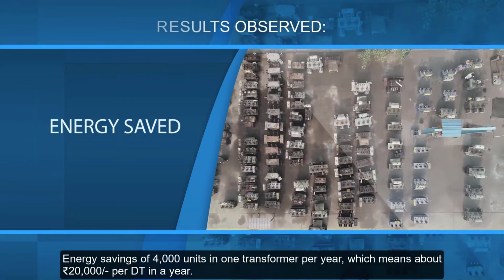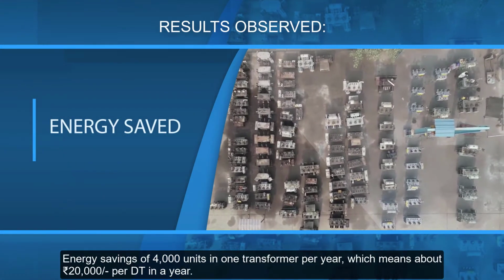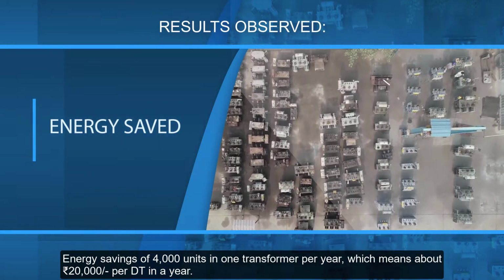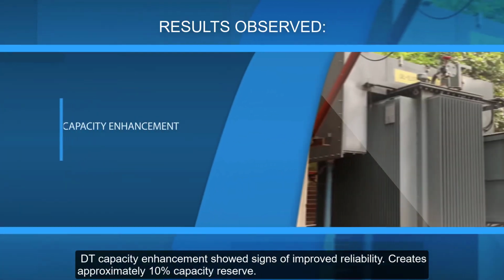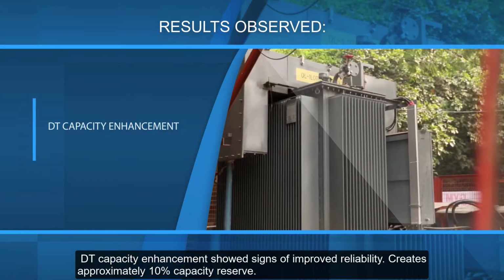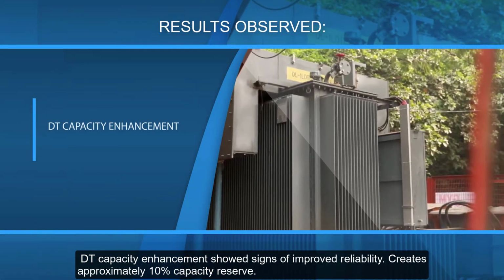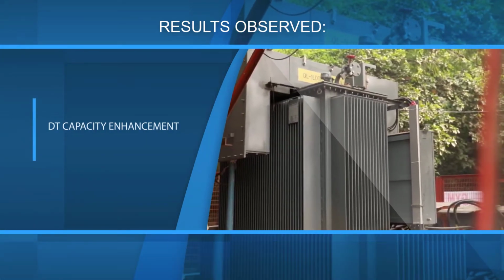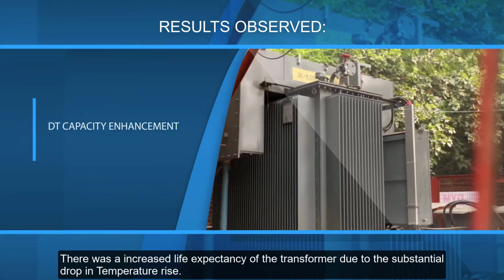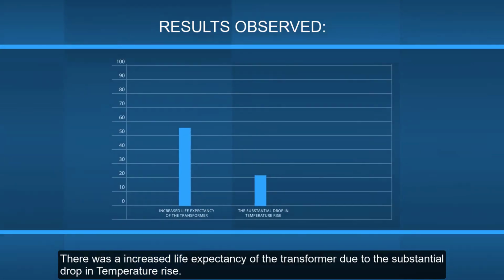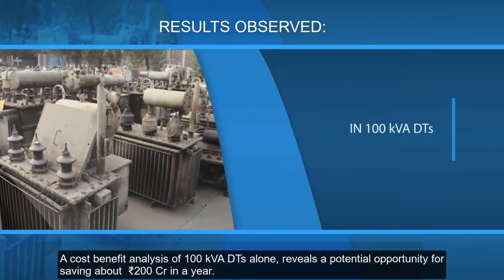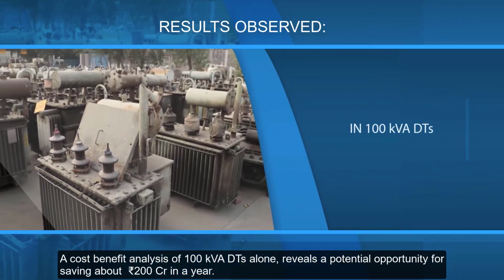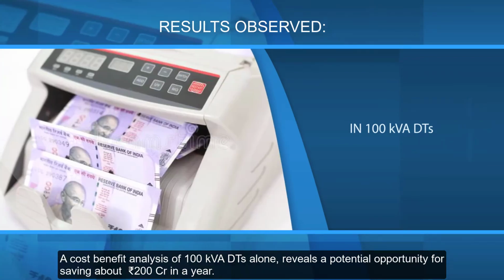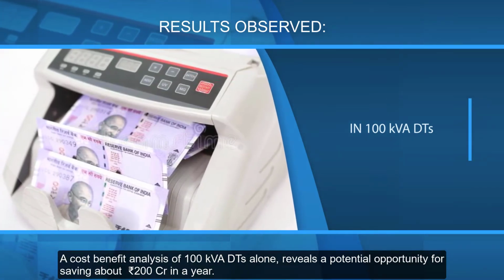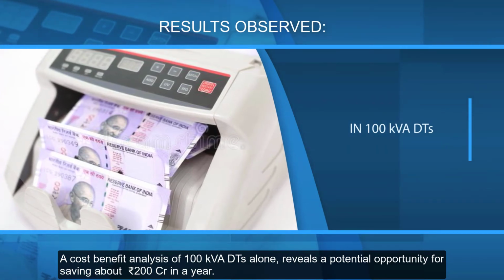Energy saved was to the extent of 4,000 units in one transformer per year, which means approximately 20,000 per DT in a year. Also, DT capacity enhancement showed signs of improved reliability and creates approximately 10% capacity reserve. There is an increased life expectancy of the transformer due to the substantial drop in temperature rise. With key assumptions based on current market trends, the cost-benefit analysis reveals that 100 kVA DTs alone have a potential opportunity for saving nearly 200 crore per year.